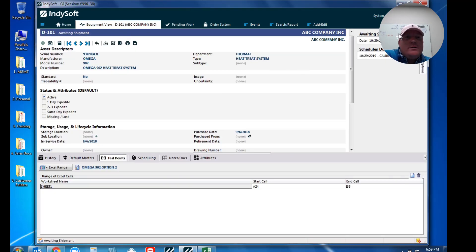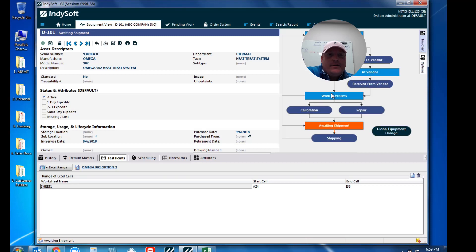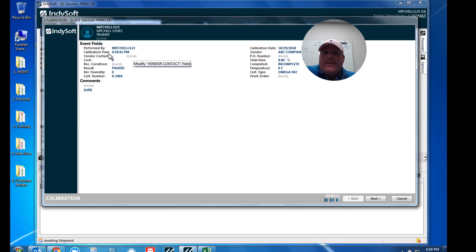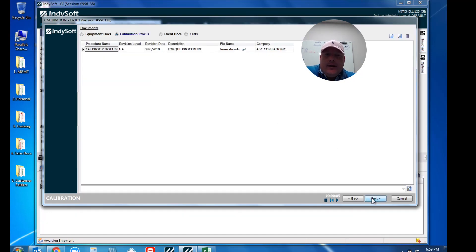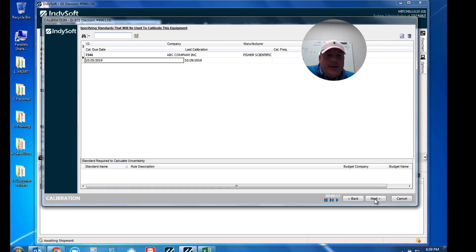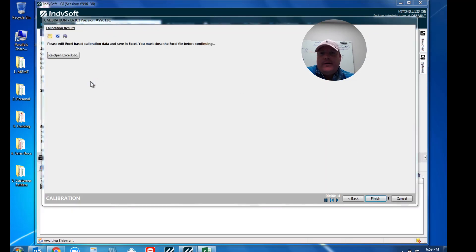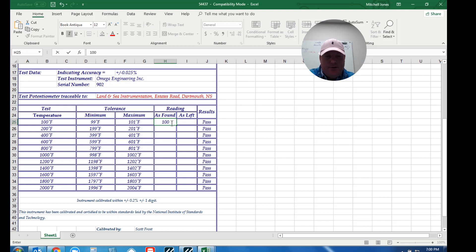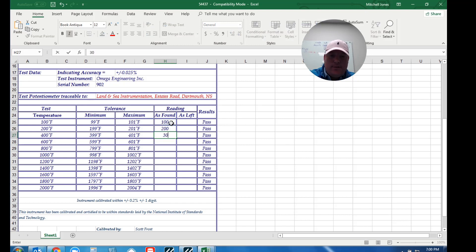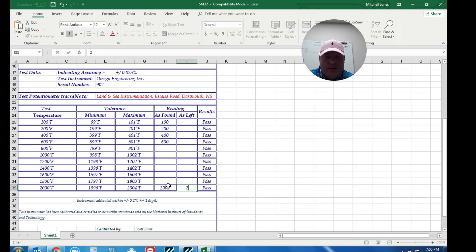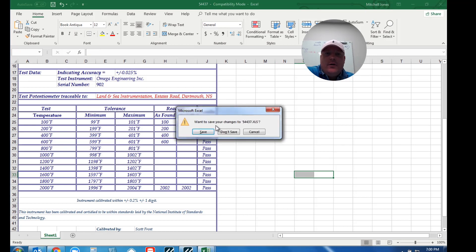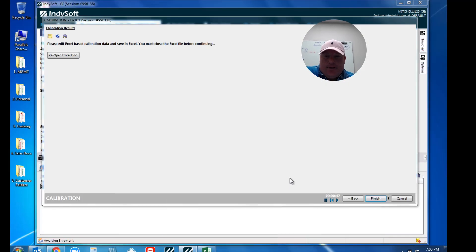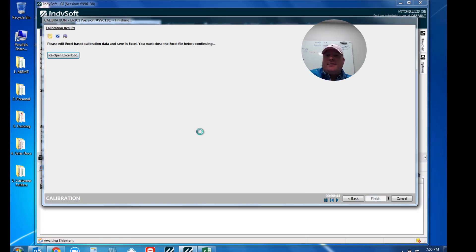So from start to finish one more time, I'll go ahead and calibrate this instrument here. We launch our calibration event just like we all normally do. You have your kind of your who, what, when, where and your nomenclature step. The secondary step is you take a look at your procedures. Then of course we have our charges, our standards if you're inputting those, and then it opens up that data sheet file. So here's a copy of my Excel file. We can actually go in and I can fill out that content there if I need to. So we'll just type in a few test points here. And just for time's sake I'm not going to fill them all out. I'm just going to jump down here to the bottom and fill out this last test point.